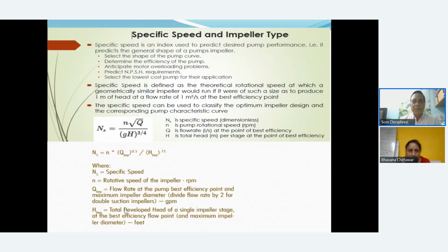Now, what is specific speed? The specific speed formula is N under root Q, where Q is the flow rate in liters per second, g is the gravitational acceleration, and H is the head in meters. So N under root Q over (gH) to the power 3/4. This is the specific speed. Once you know the Q and the H, the first thing you can find out at the design stage is the specific speed. In numeric terms, it is just the powers 0.5 and 0.75, so it's just a numeric conversion. Nothing to worry about there.